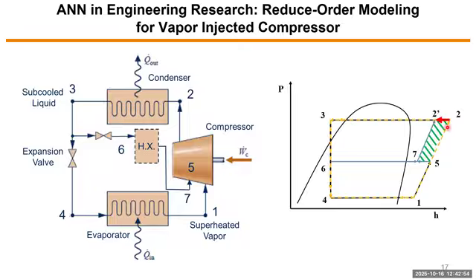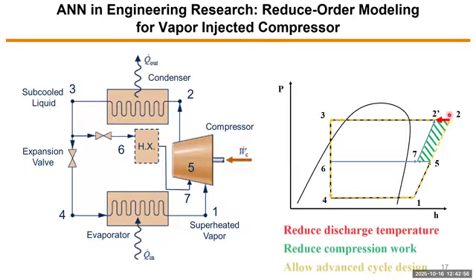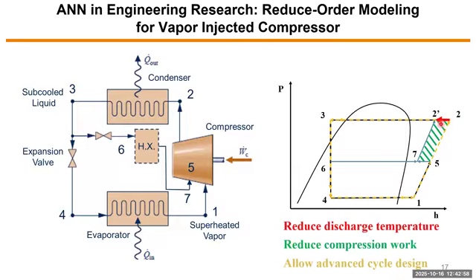So one obvious benefit you get here is a reduced discharge temperature. Originally at point 2, now you can go to 2 prime. And you can also save some compressor work. The area in the p-h diagram is indicated by this green dashed line.